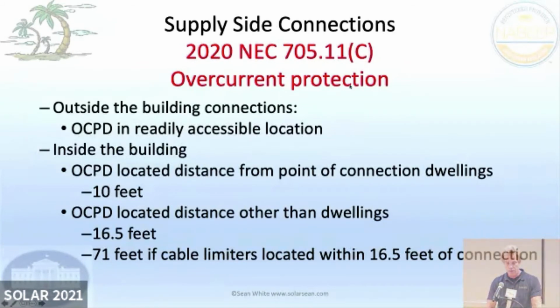And then here are some other new things too, like for overcurrent protection with supply side connections. Another thing about supply side connections is that oftentimes the slang term for that is line side tap. It's not really a tap, you don't follow the tap rules. So the correct term is supply side connection, but like half the people out there say line side tap, so you'll hear that. Outside of a building, there are not as many extra rules, but inside of a building, the overcurrent protection device must be 10 feet from the point of connection inside the building. If it's not a dwelling, so a commercial building, something like that, it would be 16.5 feet. The reason that's an odd number is because it's converted to meters.